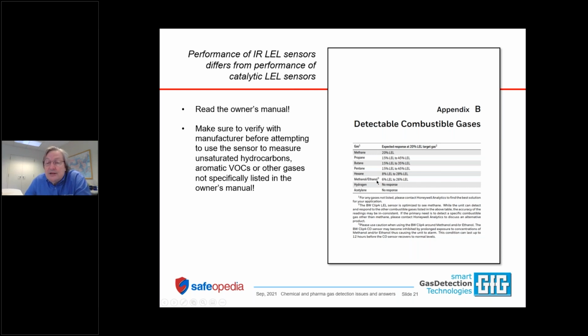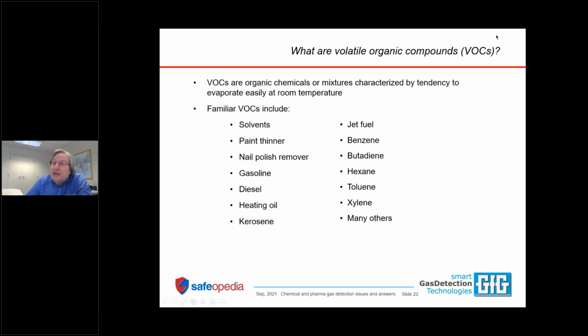For methanol and ethanol, the sensor responds very well, but again, it's kind of a qualitative response. You can have a response anywhere between 6 and 26. For hydrogen and acetylene, no response whatsoever. Different IR-LEL sensors are going to have different advice. The full-sized sensors have a much more predictable response to the gases that absorb less strongly, and also they're more expensive, and they have more sophisticated lookup tables for moving from one gas to another gas.